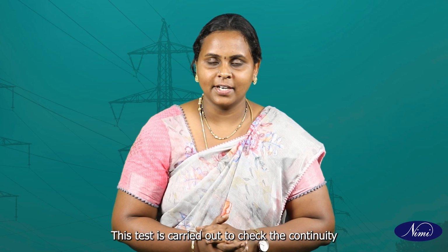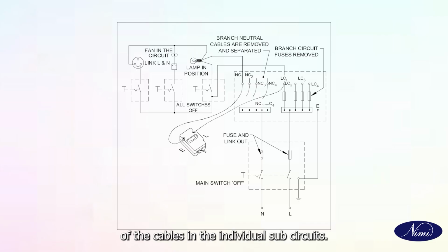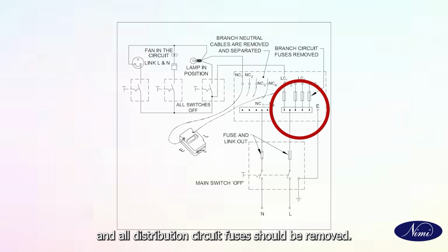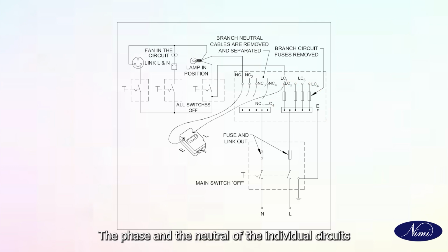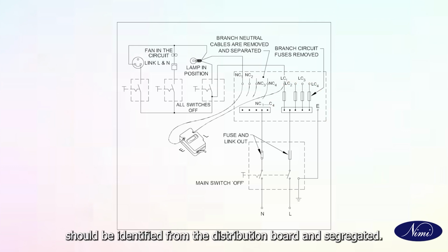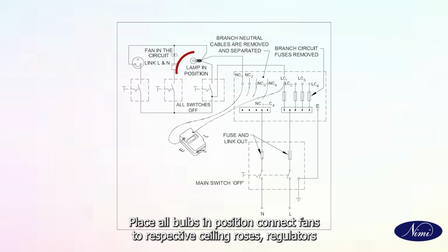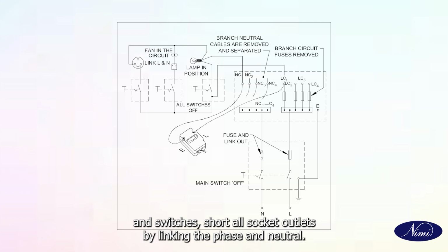Continuity or open circuit test. This test is carried out to check the continuity of the cables in the individual sub-circuits. Before conducting this test, the main and all distribution circuit fuses should be removed. The phase and the neutral of the individual circuits should be identified from the distribution board and segregated. Place all bulbs in position. Connect fans to respective ceiling roses, regulators and switches. Short all socket outlets by linking the phase and neutral.